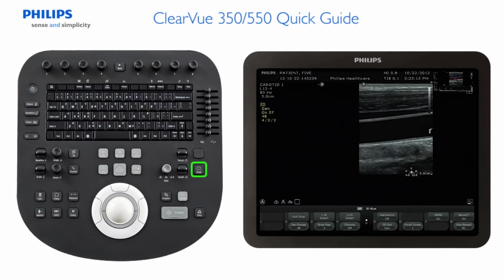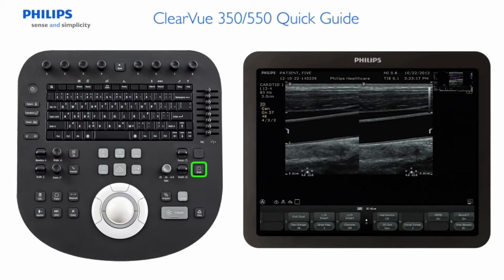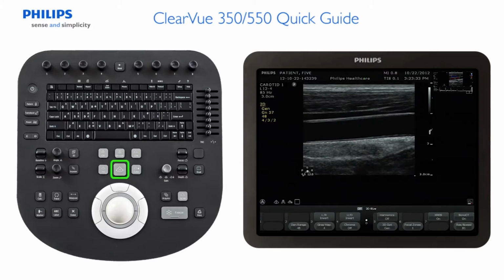Select the dual key on the control panel to activate dual imaging. To alternate between the left and the right dual imaging screens, press the Dual key. Located at the top of the image area is a red arrow that indicates the active dual buffer. To exit dual imaging, press the 2D key.